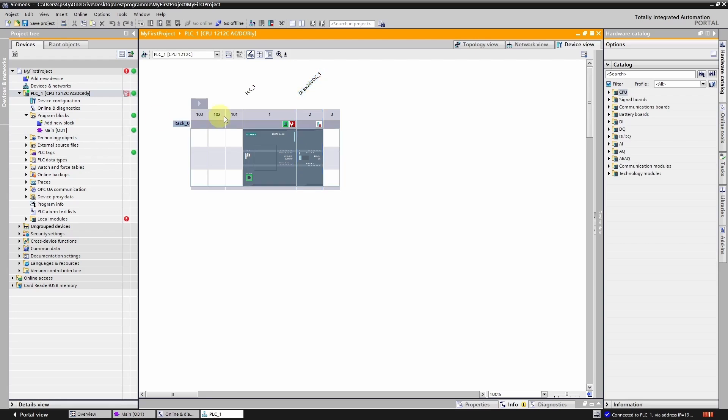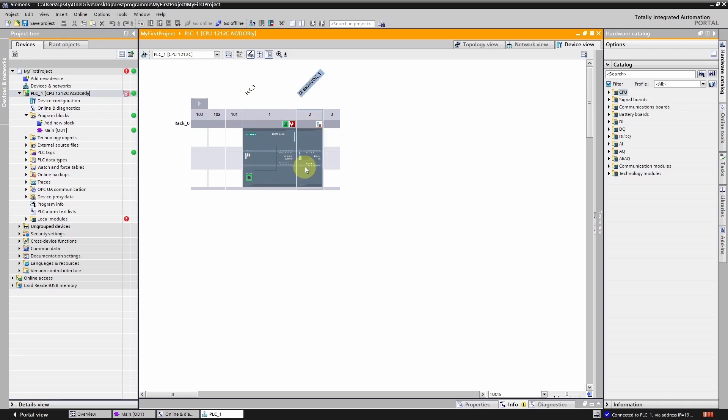Aha, I see the issue here. I have configured an expansion module that doesn't actually exist. The TIA Portal detected this and responded with a corresponding fault. I will now remove the module, transfer the complete project again and check the result.